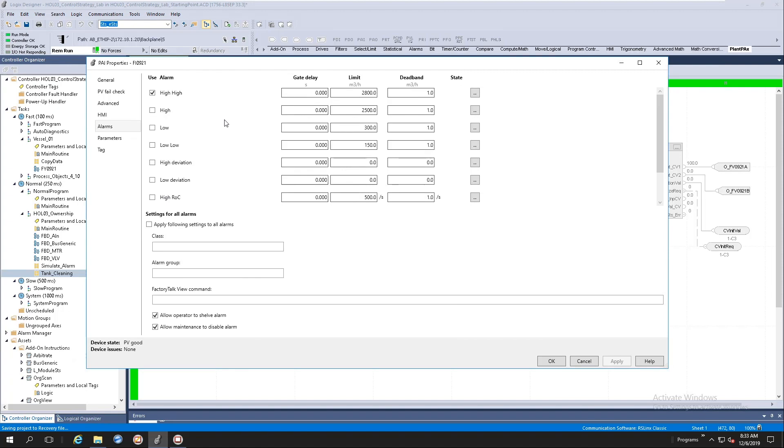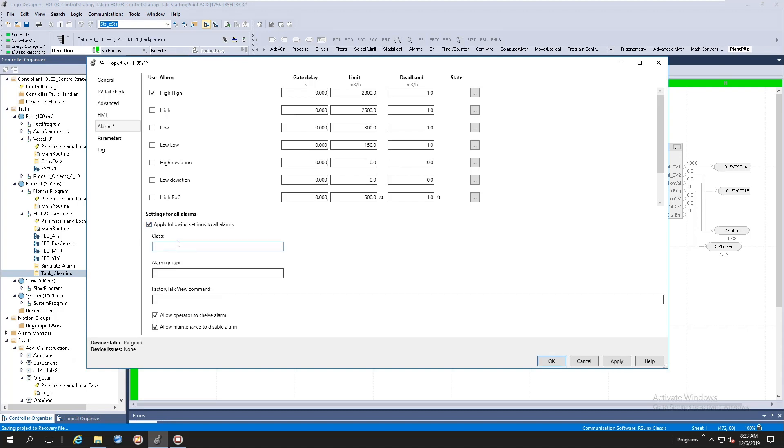Some of these alarms have common properties, for example like class, alarm group, and FactoryTalk View command. What we've done here is we've given you the capability of propagating all the alarm configurations to all the alarms. So if I say apply following settings to all alarms and I populate these values, it will actually populate it to your alarm property panel. So let's quickly look here.